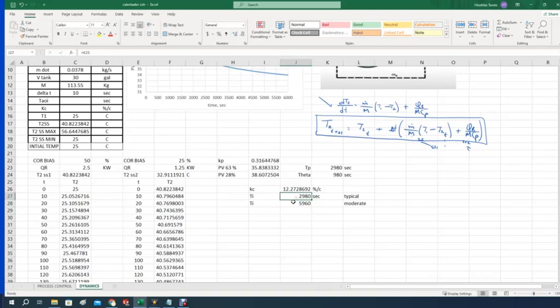You might want to use this, but if you want to really slow things down on the integral part, then you use a higher value than the one predicted by the open loop model. The open loop model is predicting 2980, and if I go with this one, the integral part would be smoother. So instead of cycling, it will try to get into the value that you want, either from above or from below, depending where you are.